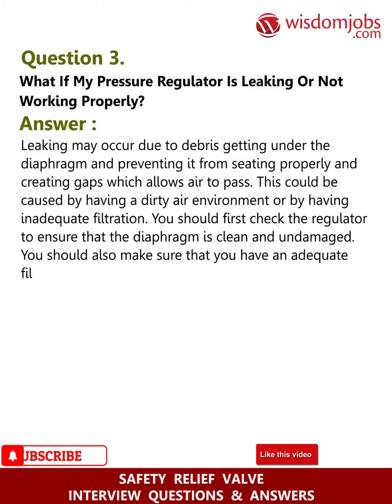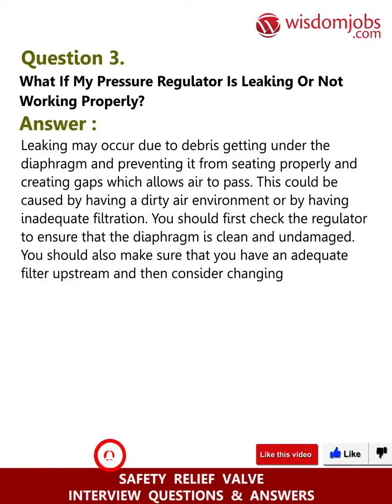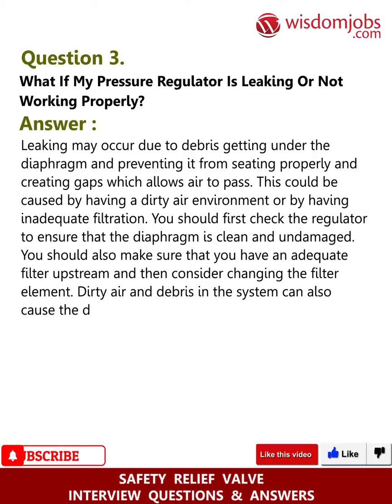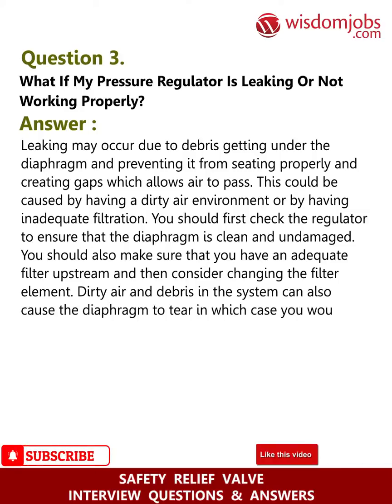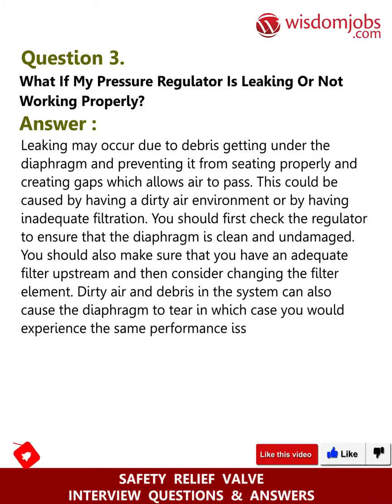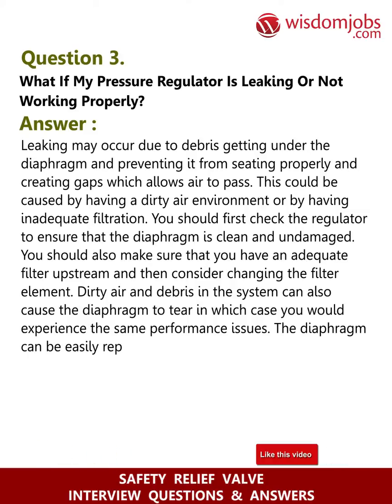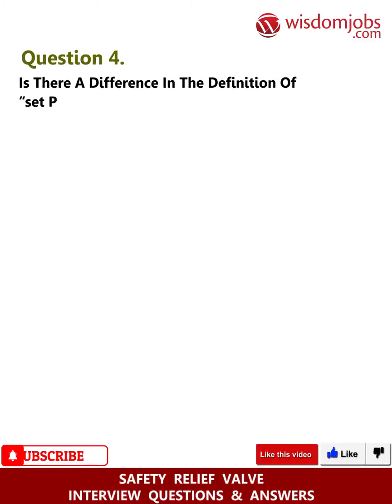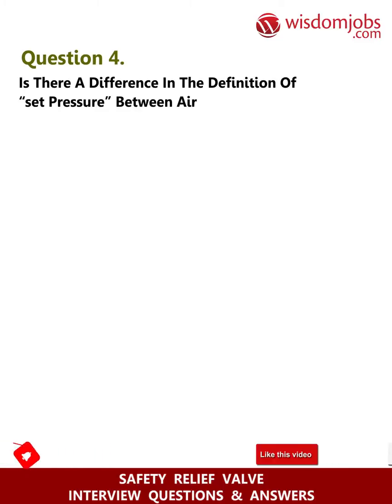You should also make sure that you have an adequate filter upstream and then consider changing the filter element. Dirty air and debris in the system can also cause the diaphragm to tear, in which case you would experience the same performance issues. The diaphragm can be easily replaced by purchasing a repair kit.